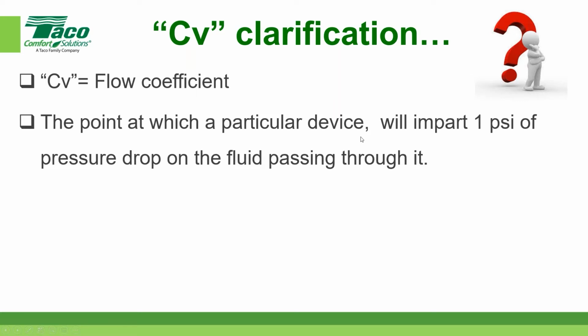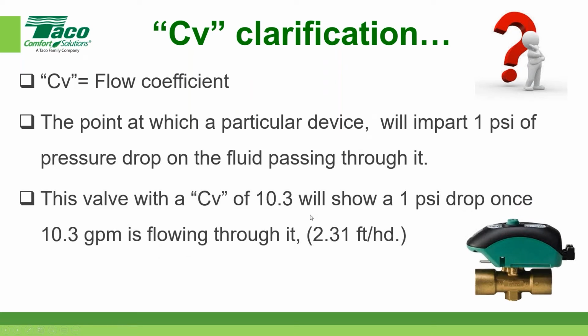Again, we put these things on test benches and we impart enough flow through the device until we get to 1 psi, and that tells us what the actual flow coefficient is. We use that as a benchmark. It's just an industry benchmark, so I can take, for instance, a Taco zone valve, and compare it against a competitor and see which one has less resistance, or which one's going to impart the least amount of friction loss to the circulator that has to pump through it. Normally, a higher number in a two-way valve like this is a good thing. For instance, this Zone Sentry 3/4 inch sweat version of it has a CV of 10.3. That means I could pump 10.3 gallons a minute through that thing, and I would only have 1 psi, or 2.31 feet of head, by that flow going through it.